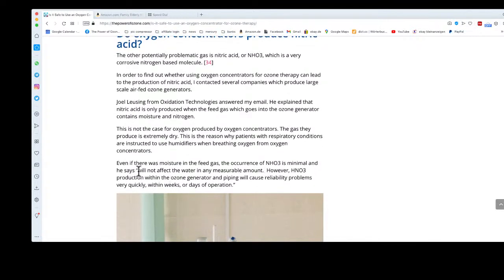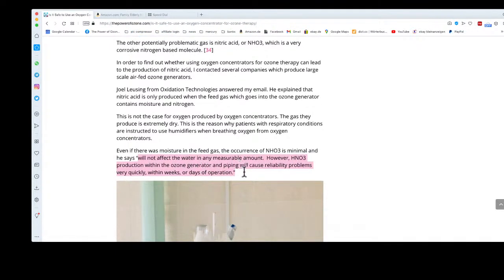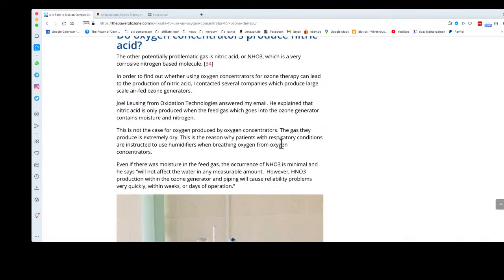And so he said, I was quoting him here: "However, HNO3 production within the ozone generator and piping will cause reliability problems very quick, within weeks or days." So yeah, if there is water and if you produce HNO3, this can corrode and this can even damage the ozone generator inside, right? But he says that the gas that oxygen concentrators produce is extremely dry. So again, this is not a concern.